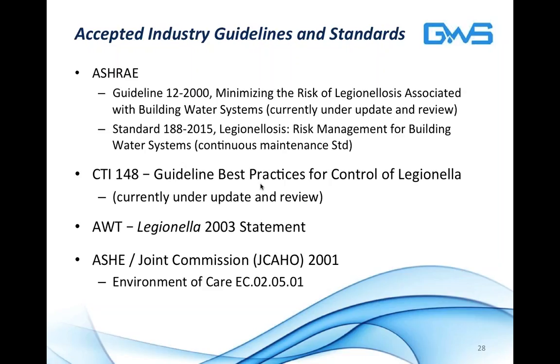CTI has 148, which is a guideline for best practices for control of Legionella, currently under update and review. In 2003, AWT issued their Legionella statement, and ASHE and the Joint Commission in 2001 established an environment of care that includes maintaining your cooling towers appropriately to prevent proliferation of not only Legionella but other pathogens found in cooling water.